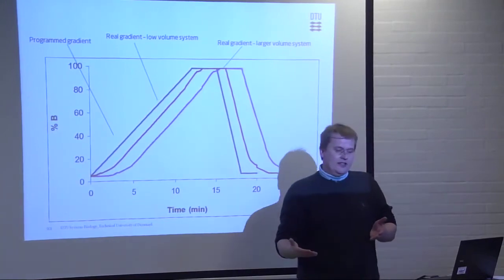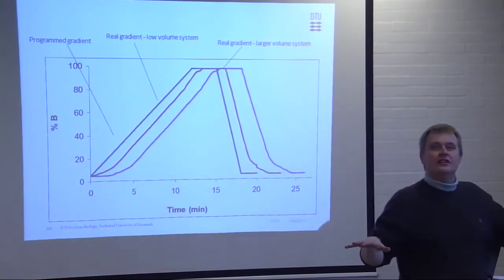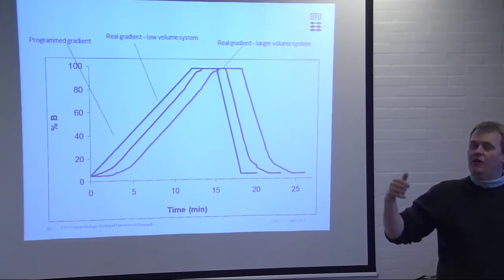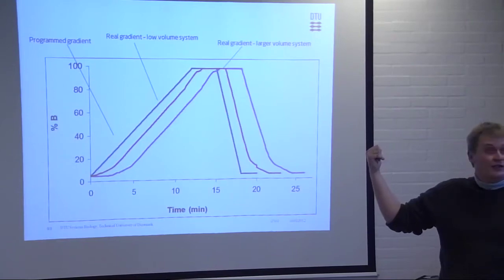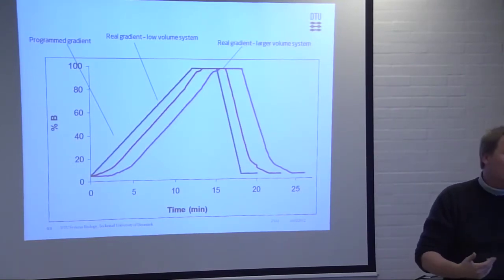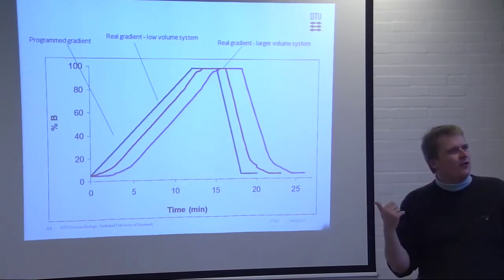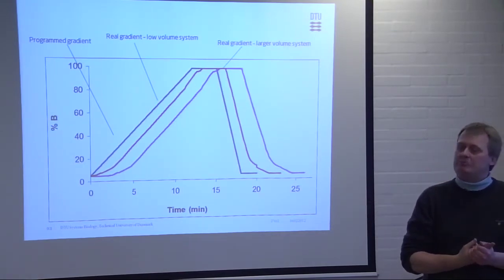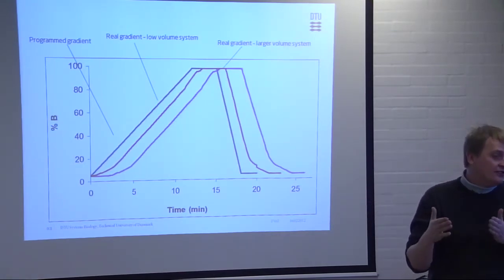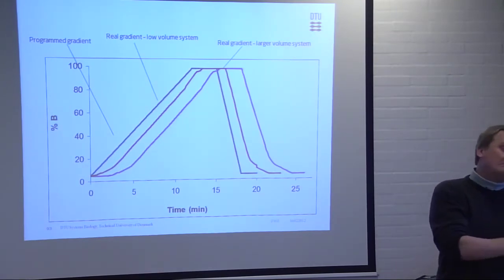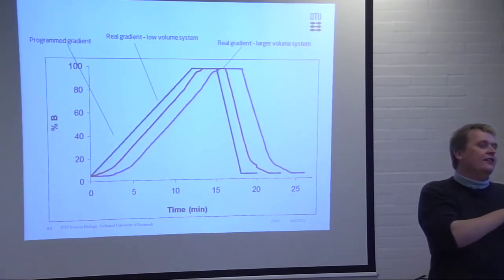So it also means that you can think that you have two identical HPLC systems in the lab, and they may not be so. Also, another thing is that the scientific papers you read, that this was done on a Waters Acquity, or an Agilent 1100 system, they're probably not going to write which mixer size they have. So, you cannot use their retention times, even though you buy the same column, because you don't know the delay of their gradients.